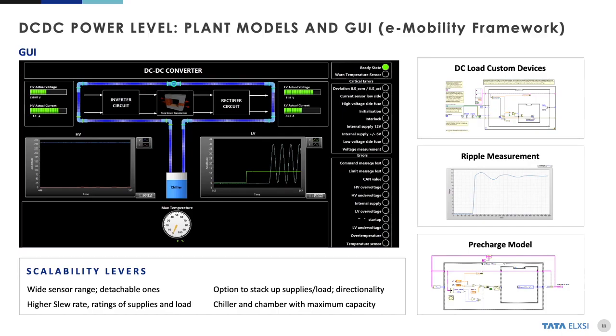Scalability levers for DC-DC HILS are selecting sensors with a wide operating range, ones which can be detached from the power circuit, and selecting power supplies and loads which can be stacked up in future for increasing the rating, ones which have bidirectional capability. Individually, each should have a high slew rate as well as a large operating range.